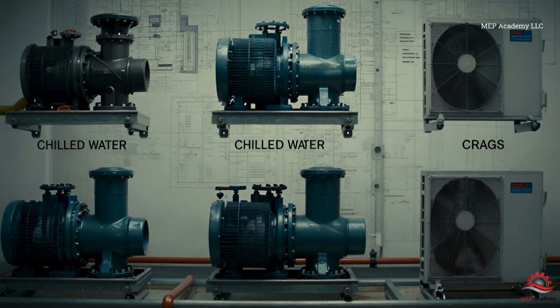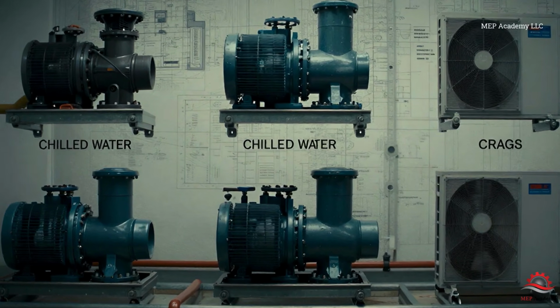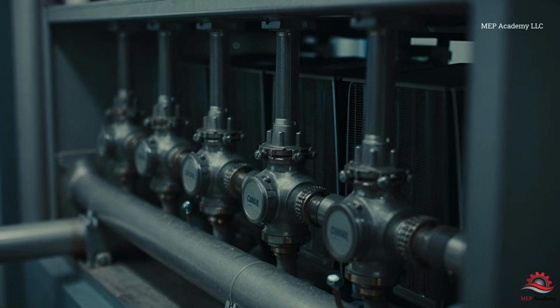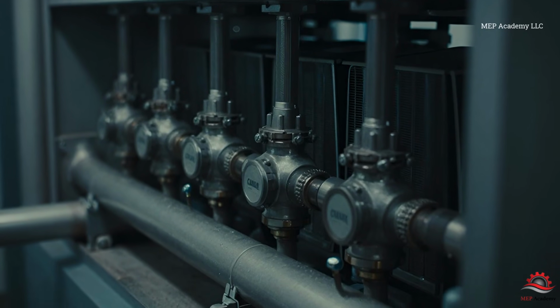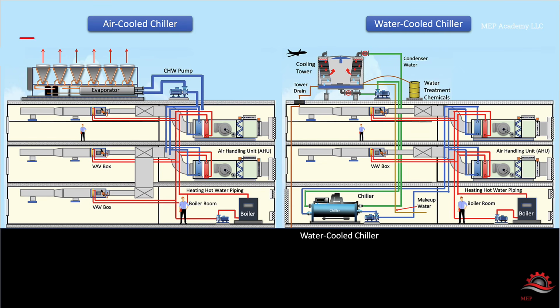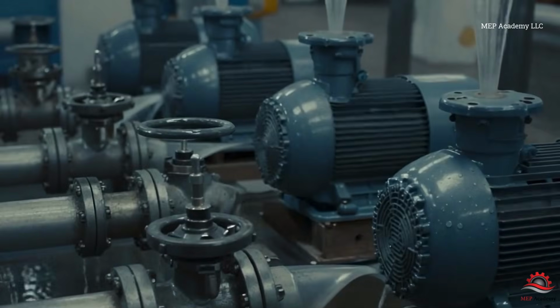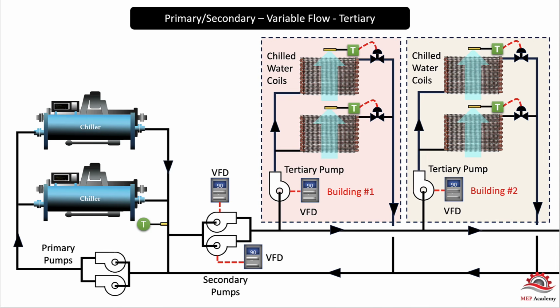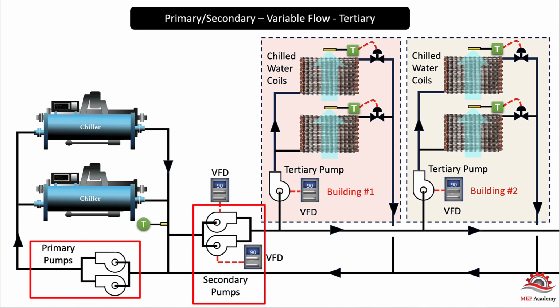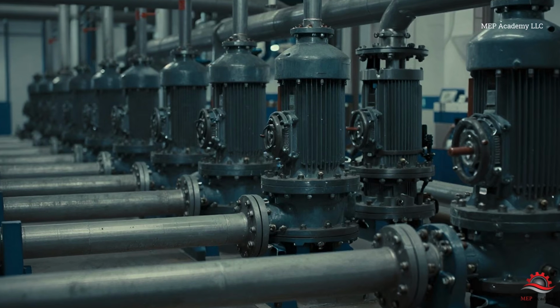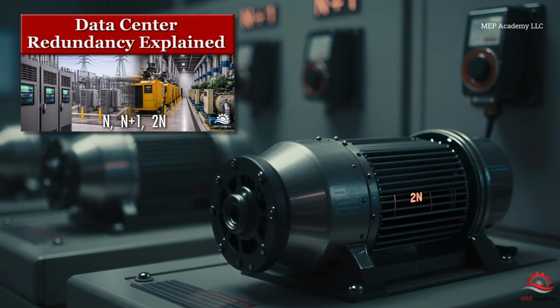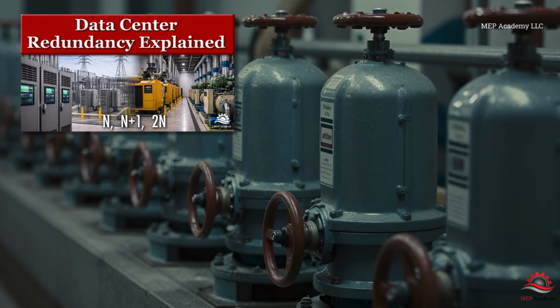Key components of the system. Let's break this system down into its major components. Chillers are the heart of the system. They remove heat from the water using refrigeration cycles, similar to a giant air conditioner. There are two common types you'll see: air-cooled chillers and water-cooled chillers. Air-cooled chillers reject heat directly to the outside air. Water-cooled systems use cooling towers, which we'll touch on shortly. Pumps keep the water moving through the system. You typically have primary pumps, circulating water through the chiller. Secondary pumps, delivering water to the building. In many data centers, these systems are designed with redundancy like N+1 or 2N pumping configurations. So even if a pump fails, cooling continues.